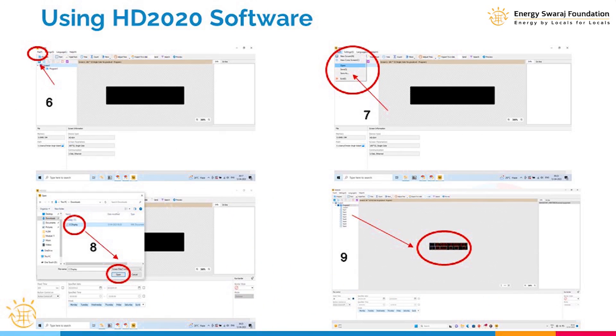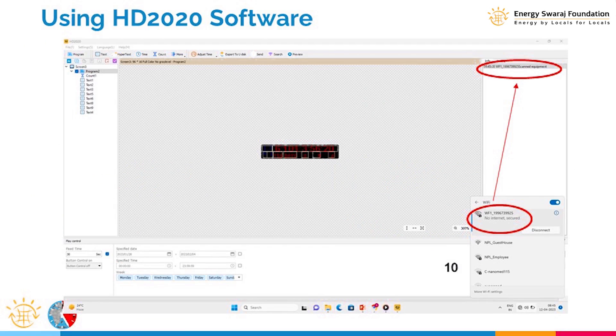Open this file on your computer using the software HD 2020. Once you open it in HD 2020, every setting is already in place. Now you need to connect with the controller to send the program to the controller of your climate clock. Switch on your laptop's Wi-Fi and search for the Wi-Fi of the controller.